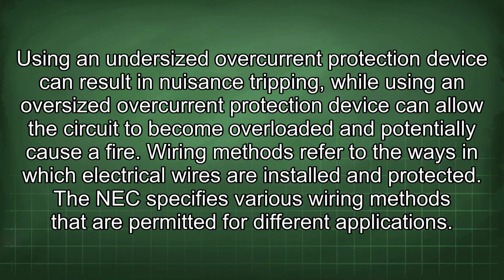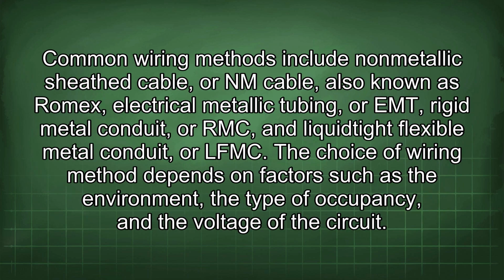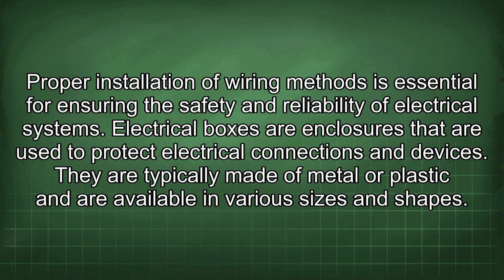Wiring methods refer to the ways in which electrical wires are installed and protected. The NEC specifies various wiring methods that are permitted for different applications. Common wiring methods include non-metallic sheath cable, or NM cable, also known as Romex, electrical metallic tubing, or EMT, rigid metal conduit, or RMC, and liquidtight flexible metal conduit, or LFMC. The choice of wiring method depends on factors such as the environment, the type of occupancy, and the voltage of the circuit. Proper installation of wiring methods is essential for ensuring the safety and reliability of electrical systems.